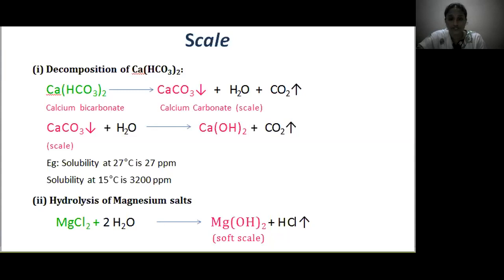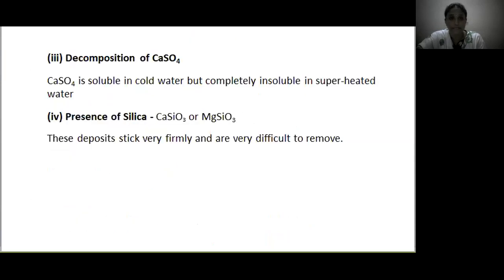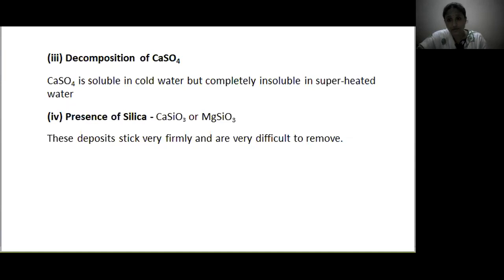Another cause is hydrolysis of magnesium salts: magnesium chloride undergoes hydrolysis to give a soft scale called magnesium hydroxide. Decomposition of calcium sulphate is also a reason — the solubility of calcium sulphate in water decreases with increasing temperature, so it is soluble in cold water but completely insoluble in superheated water, depositing as hard scale on heated portions of the boiler. This is the main cause of scale in high-pressure boilers. Additionally, silica present in small quantities deposits as calcium silicate or magnesium silicate, which are very firmly attached and difficult to remove. The important source of silica in water is the sand filter.